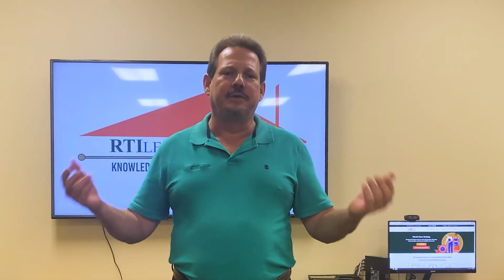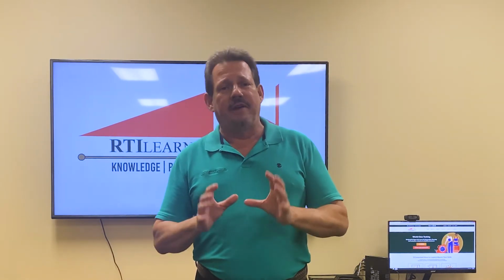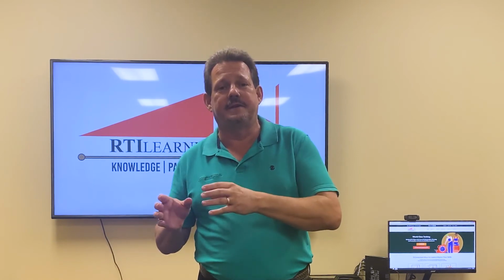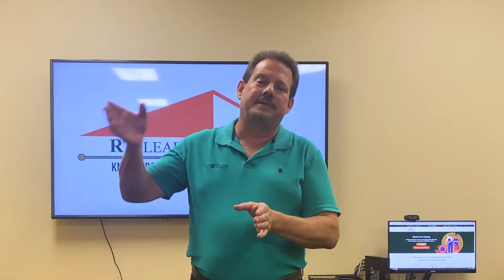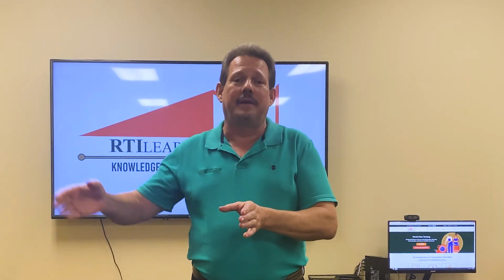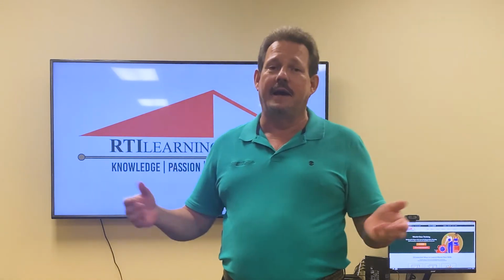Very simply, if you've got a whole home where we're talking about smoke or pet odors or something like that, or an entire commercial office space that has an odor due to a process or whatever else, best place to do it is get into a more professional commercial grade system and place it in the air conditioning system return air. So that way, every time the air conditioning system runs, heating system runs, it's going to be picking up that masking and pairing agent and distributing it through the building, thus treating the entire environment.